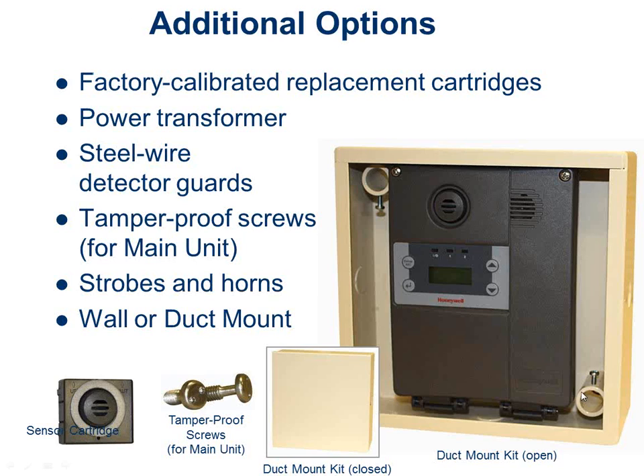Depending on the application, you may want to measure stuff in the duct. In general, as a rule of thumb, you want to measure stuff in the space because that's where the people actually are. Measuring the duct is a second choice if I can't put it in the space because there's a problem, hose, spray, water, whatever, that kind of thing.